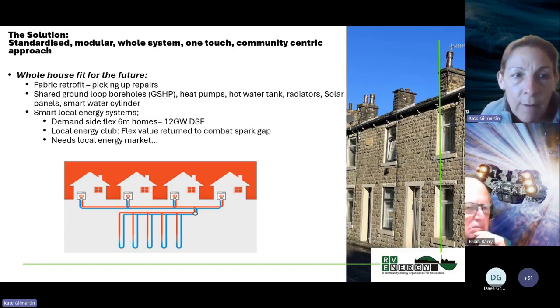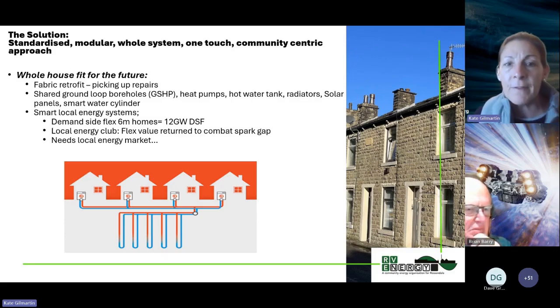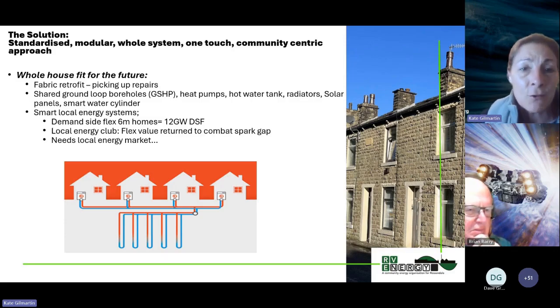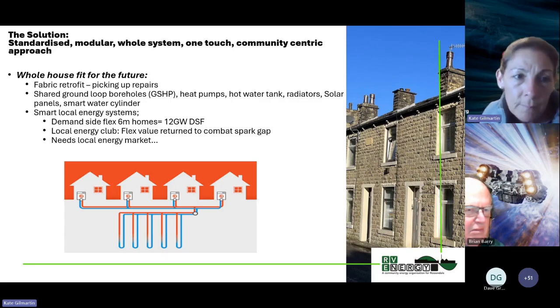So we're looking at shared ground loops, basically 150-metre boreholes that go in the street. We expect one borehole to have a heat load of about 12 kilowatts, enough to do 2 terraced homes. Obviously different geology gives different results - 150 metres in one area, it might be 100 in another, 200 in another. Essentially those are linked together across a cluster, which gives you that kind of diversity across the cluster.